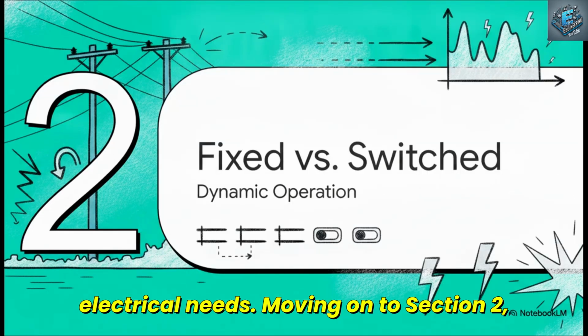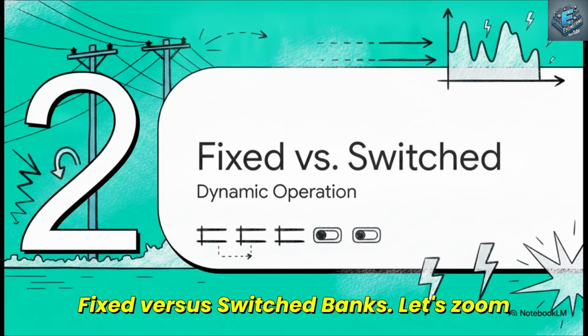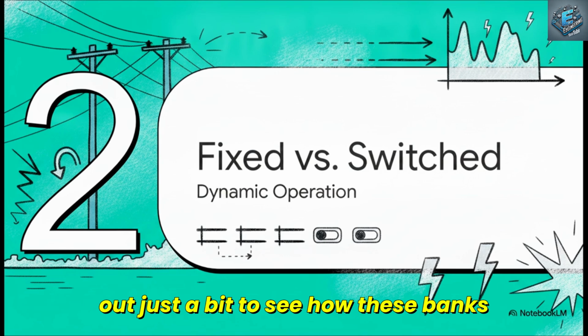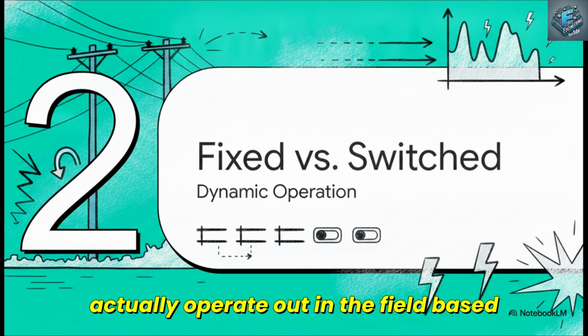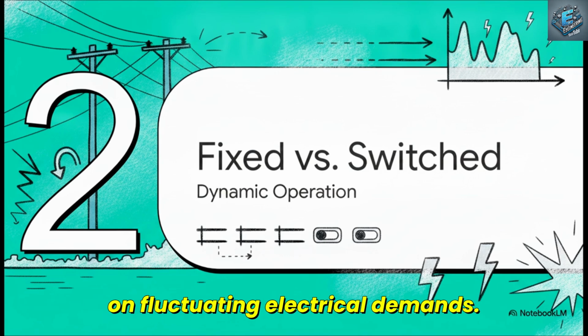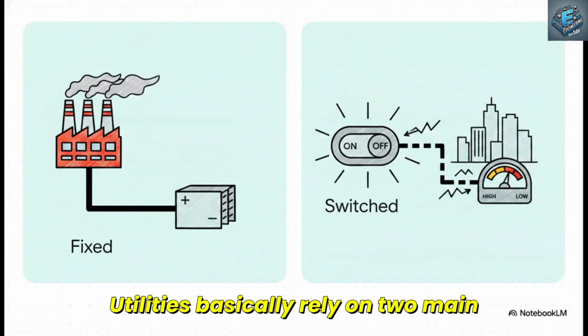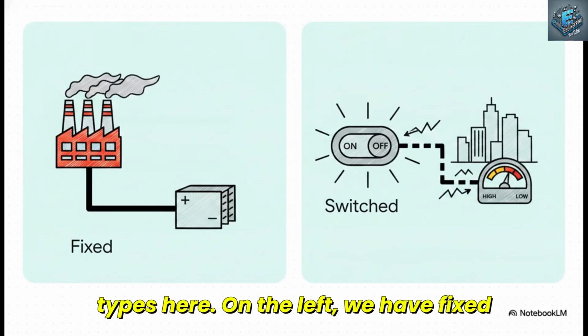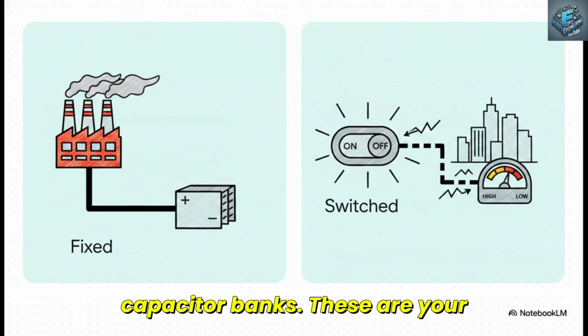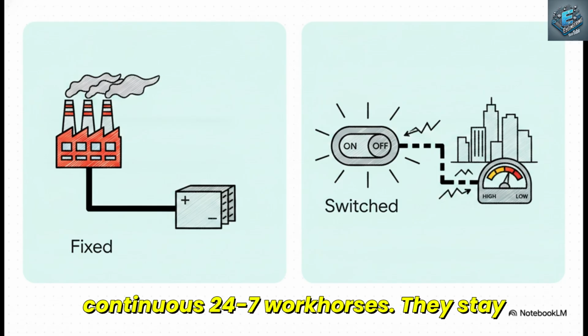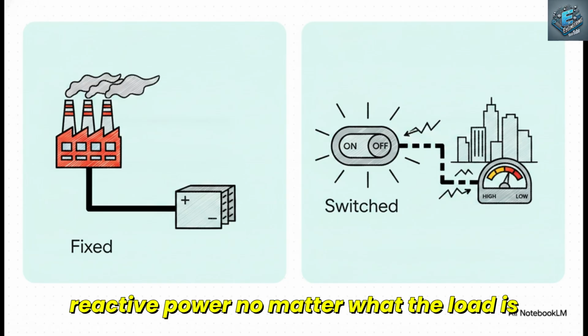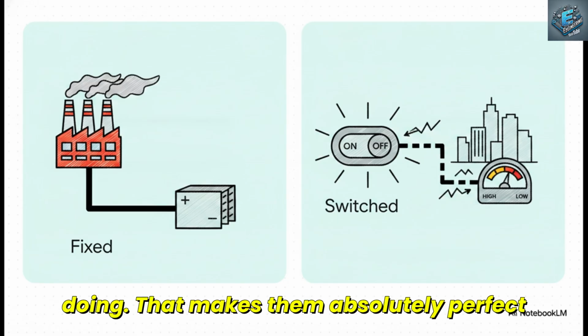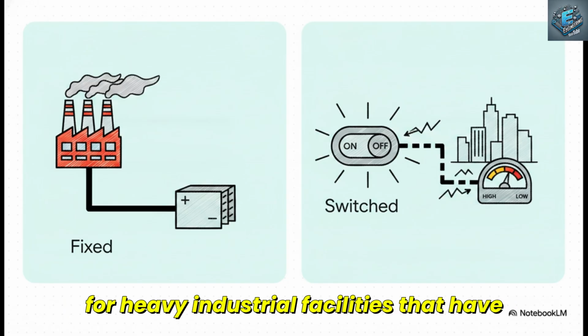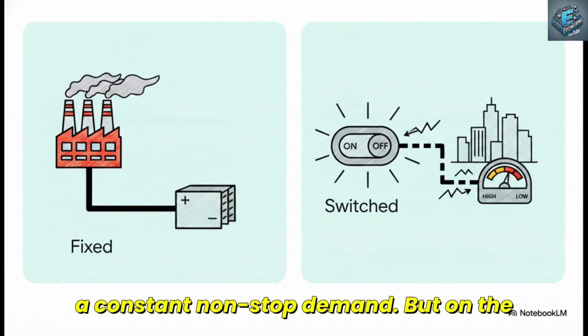Moving on to Section 2, Fixed versus Switched Banks. Let's zoom out just a bit to see how these banks actually operate out in the field based on fluctuating electrical demands. Utilities basically rely on two main types here. On the left, we have fixed capacitor banks. These are your continuous 24/7 workhorses. They stay connected all the time, pumping out reactive power no matter what the load is doing. That makes them absolutely perfect for heavy industrial facilities that have a constant, non-stop demand.